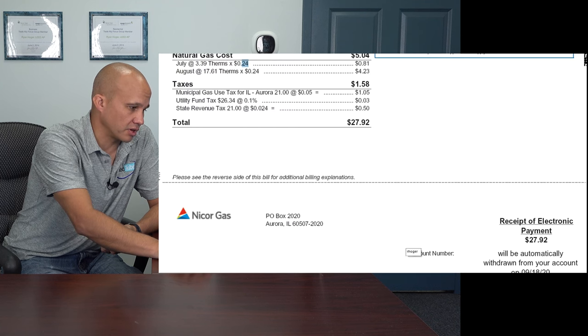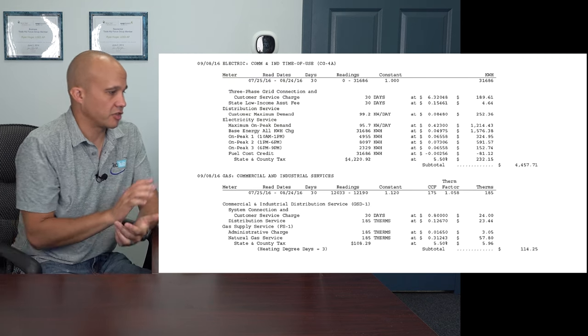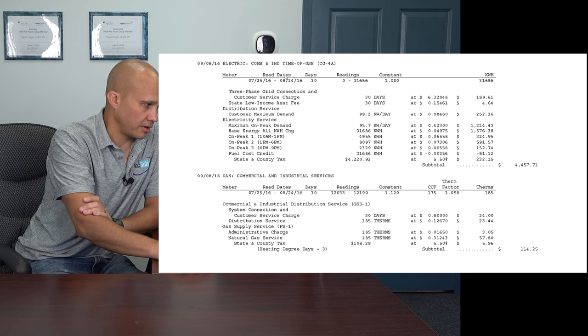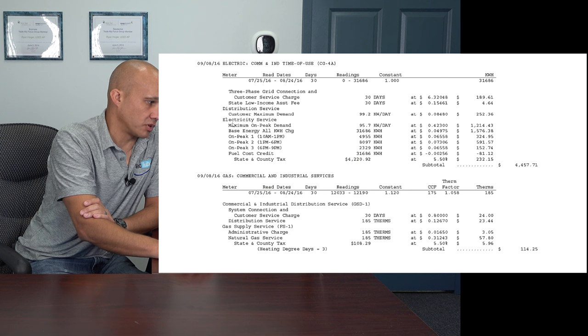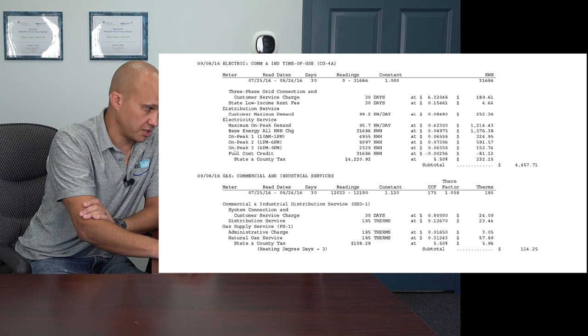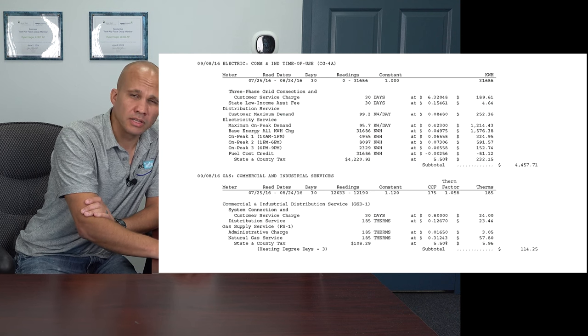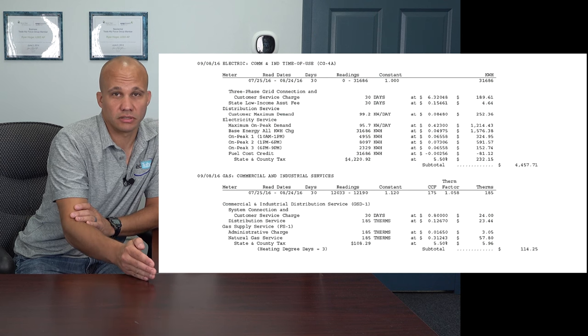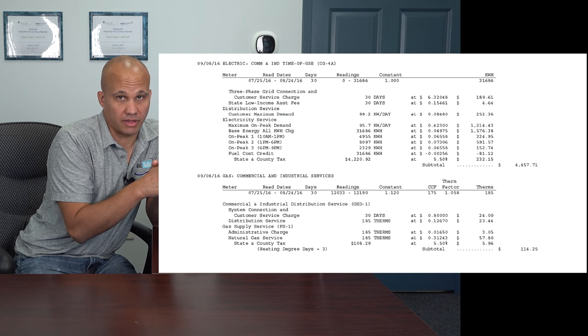So that's the way your gas bill works — same as your electric bill. Commercially, it's a slightly different discussion. This is a bill from a customer up in Wisconsin — a summertime example where they have gas and electric from the same provider. Looking at the electric part: there's a separate charge for distribution versus actual energy consumption, as with most utilities. But commercially, you're also paying for KWH — the total energy you're using — and KW, the highest peak power demand.